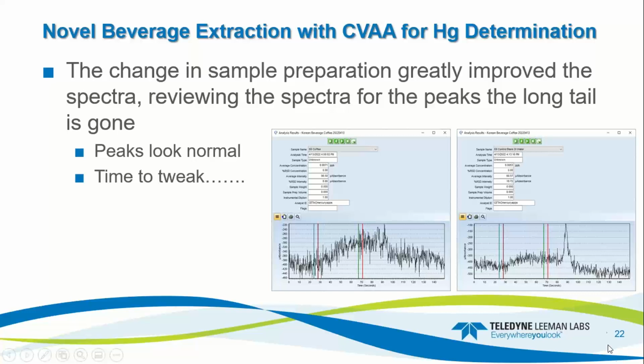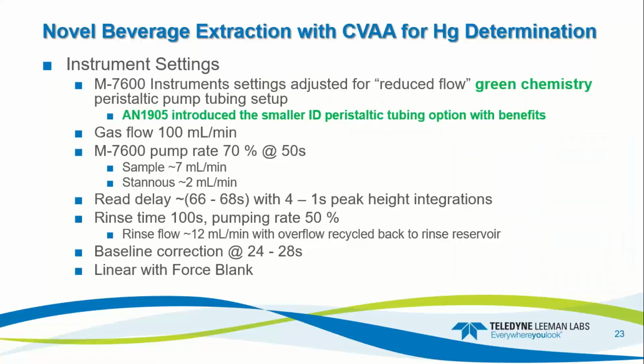And again, we are down at the trace level for this, so this is at the bottom end of detection for the system, in the 1 to 5 nanogram per liter range of detection. So I decided I was going to tweak the instrument a little bit more, still using the green chemistry pump, the smaller ID pumps, that's reducing the waste by 40%, reducing the stannous uptake by 53%. My gas flow is at 100 mils per minute. Pump rate, I went to 70% to put a little more load into the system, but I stayed at 50 seconds. So now I'm using approximately 7 milliliters per minute sample, and stannous is approximately 2 milliliters per minute.